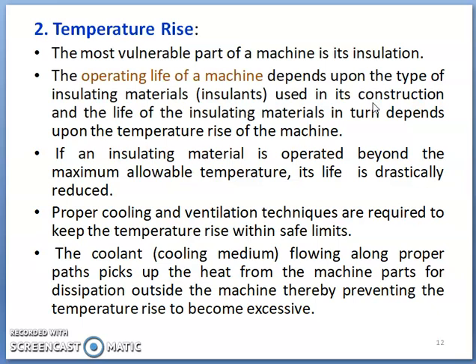Choice of insulating material and its class is very important, particularly considering temperature rise, because whatever loss is there in the machine appears in the form of heat, causing a temperature rise that must be within safe limits. A machine designed for higher output must use a better class of insulating material. The operating life of a machine depends upon the type of insulating material used in its construction, and in turn the life of that insulating material depends upon the temperature rise of the machine. If any insulating material is operated beyond the maximum allowable temperature, its life is drastically reduced.